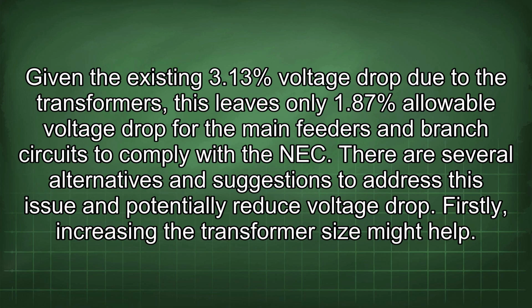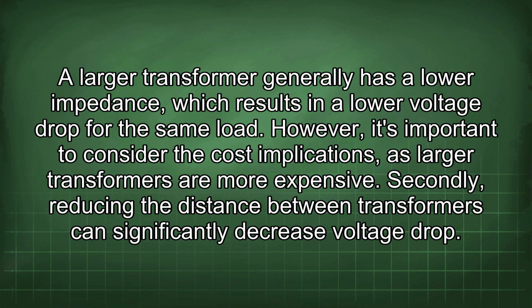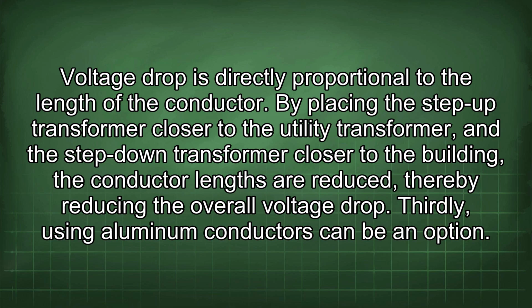There are several alternatives and suggestions to address this issue and potentially reduce voltage drop. Firstly, increasing the transformer size might help. A larger transformer generally has a lower impedance, which results in a lower voltage drop for the same load. However, it's important to consider the cost implications, as larger transformers are more expensive. Secondly, reducing the distance between transformers can significantly decrease voltage drop. Voltage drop is directly proportional to the length of the conductor. By placing the step-up transformer closer to the utility transformer and the step-down transformer closer to the building, the conductor lengths are reduced, thereby reducing the overall voltage drop.